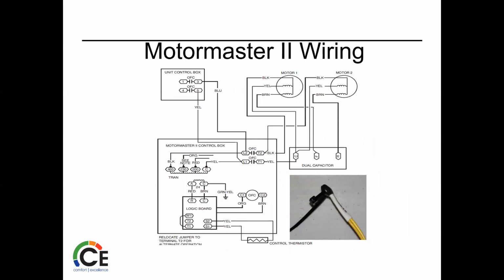Wiring, again, since this has a control box and there are some fixed places. So we've got the unit control box, which is sending power down to the outdoor fan contactor, right where that comes in. So we're powering that. We're breaking the motor leads, which again, sometimes we have to watch what capacitor we have and change that. And then that's how, depending on the thermistors, it runs a fan or turns it off. So you're just breaking that line so that if the Motor Master doesn't need to operate, the fans run normal. If it sees a point that, hey, we're getting too cold, it shuts down the fan and everything else keeps running. And that's the basic thing of any low ambient control.